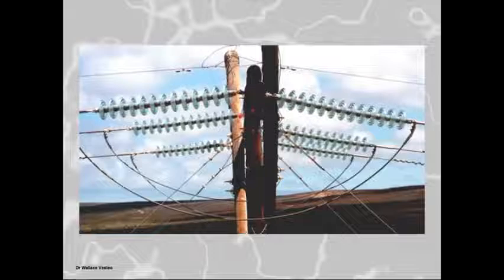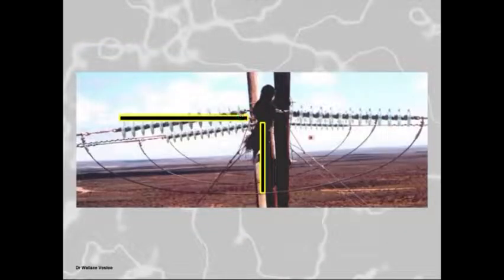But anyhow, they said it's that, and if you take a look, you can see also the distance to ground on the tension insulator, and that for the actual jumper. Now, when I went to the old guy that designed the line, who has unfortunately passed away, he said to me, "But Wallace, there's something big wrong with this line construction, because when I designed it, these jumpers had ample spacing and it was all good and everything was perfect."